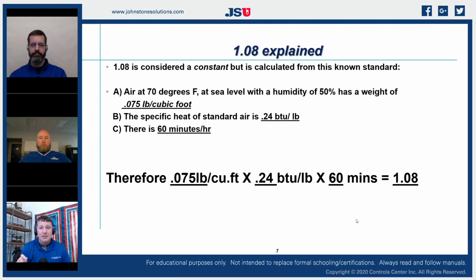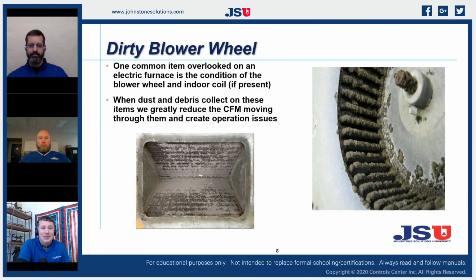But for standard measurements, the reason we call it standard air is because it is a reference point for most of the air that we work with. It is an average. So whenever you see that 1.08 and someone says that it is a constant, well, it's somewhat of a constant for our industry, but it is variable, right? So it's important to know how we're moving our air.